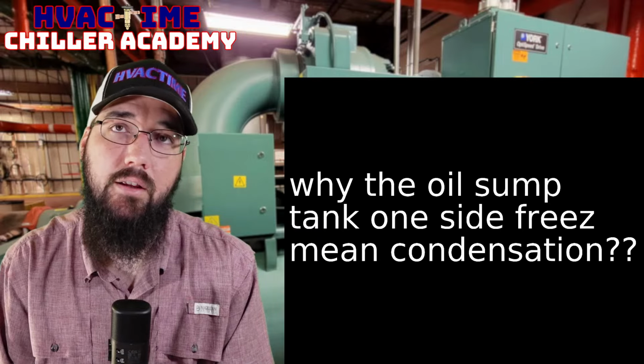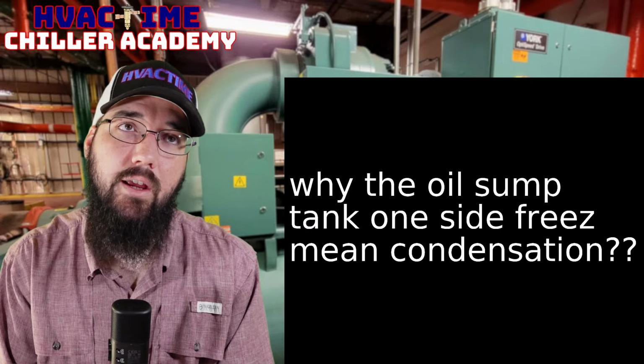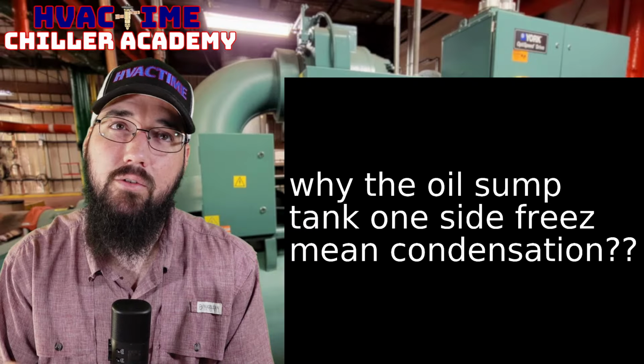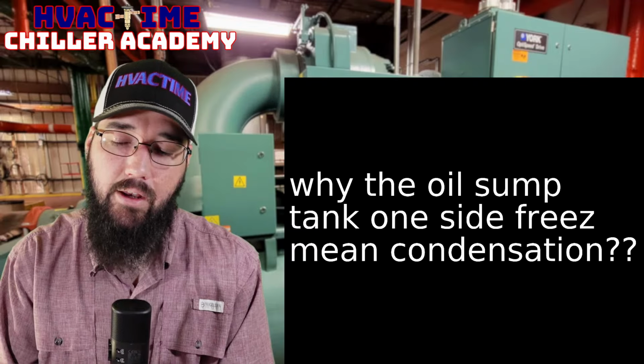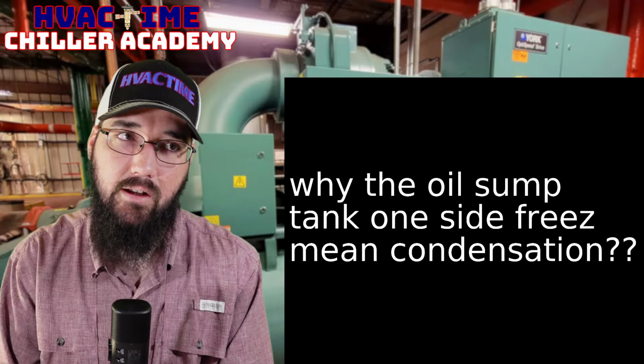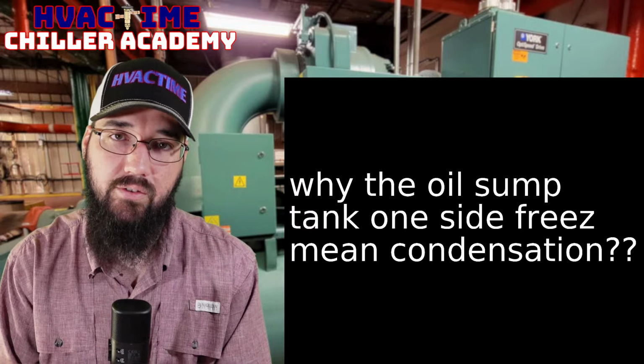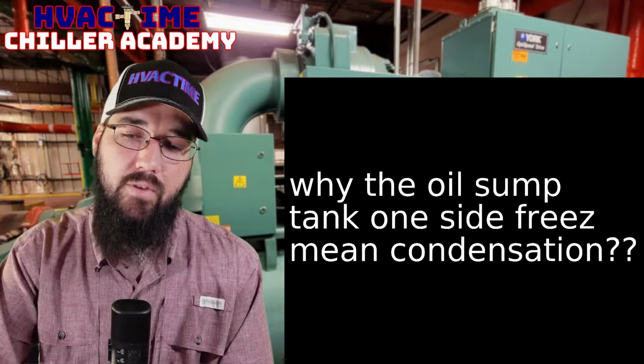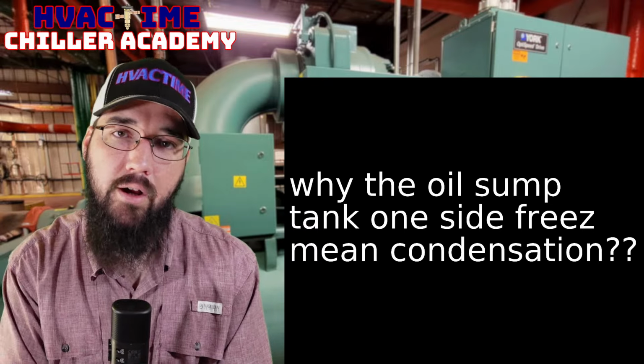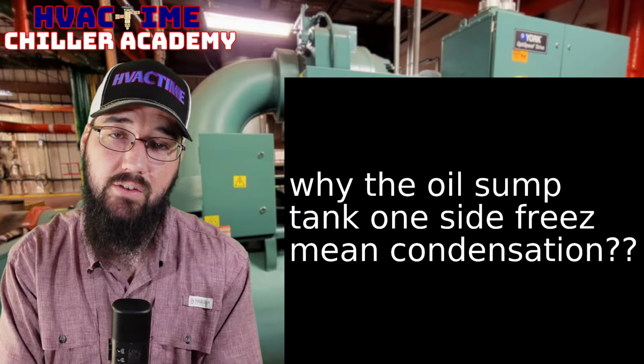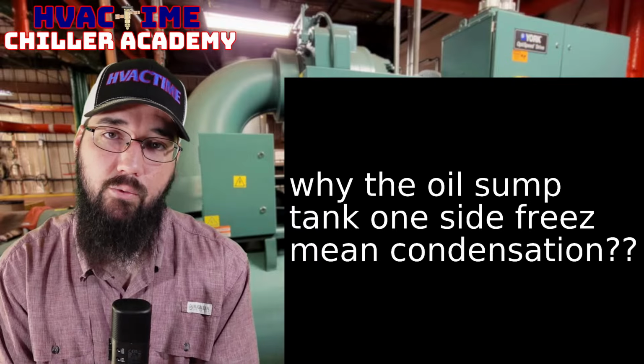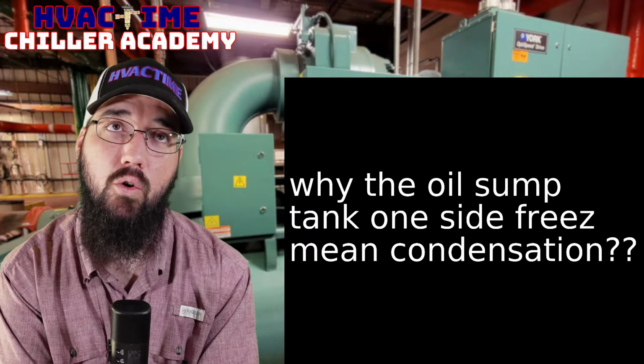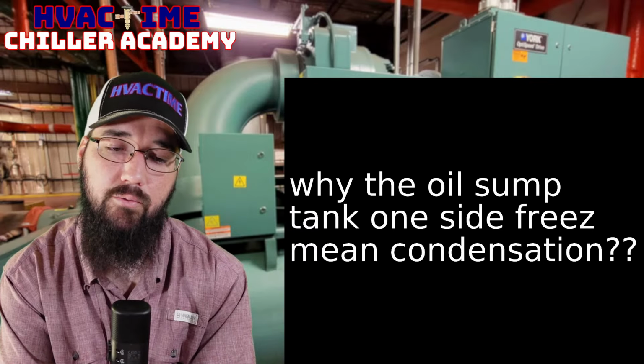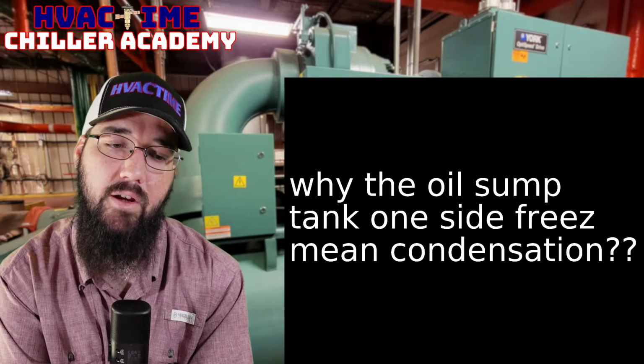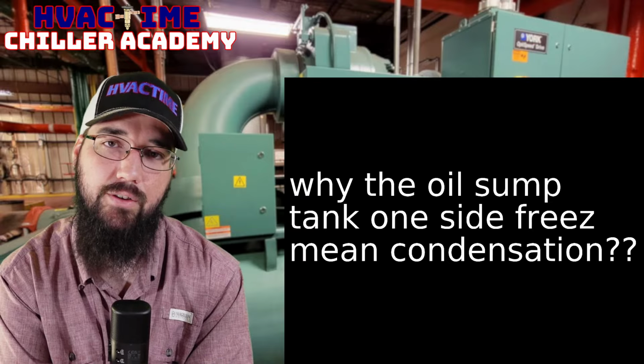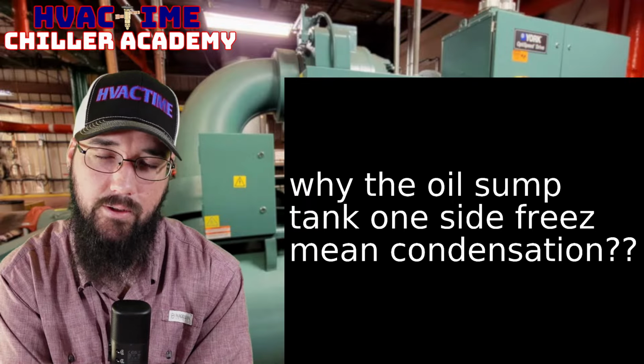It's only meant to be, what is it, a quarter to half turn to a maximum of two turns open, and you're supposed to manually set that oil return valve on the Trane centrifugals, so that you limit how much of that liquid refrigerant is getting pushed in. And what you'll see as a symptom, one of two things is happening when you see the eductor block and the oil return filter, which is a filter dryer. Okay, so that's where your dryer is on the CV system, in the eductor line. That's the big canister looking thing that's in series in that circuit.